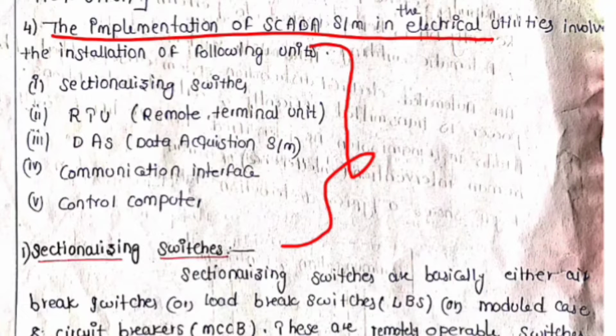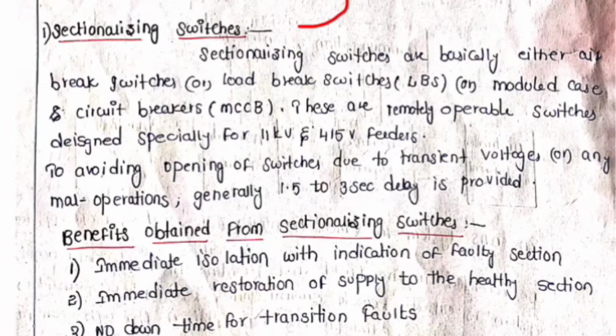Coming to them one by one, sectionalizing switches. The sectionalizing switches are basically either air break switches, load break switches or moulded case circuit breakers, normally open or normally closed. These are remotely operated switches designed specially for 11 kV and 415 V feeders. These sectionalizing switches play an important role whenever a fault occurs. If a fault occurs in one feeder, the adjacent feeder can be connected by using tie and sectionalizing switches.